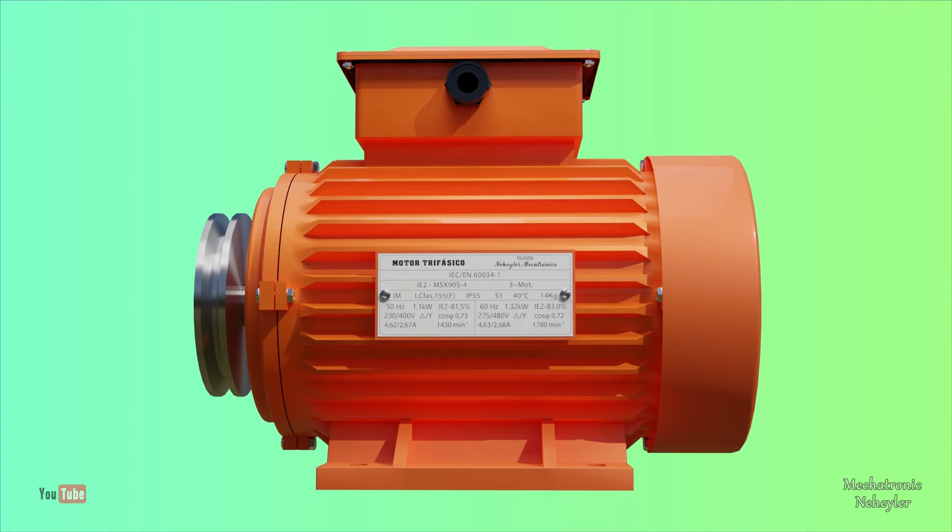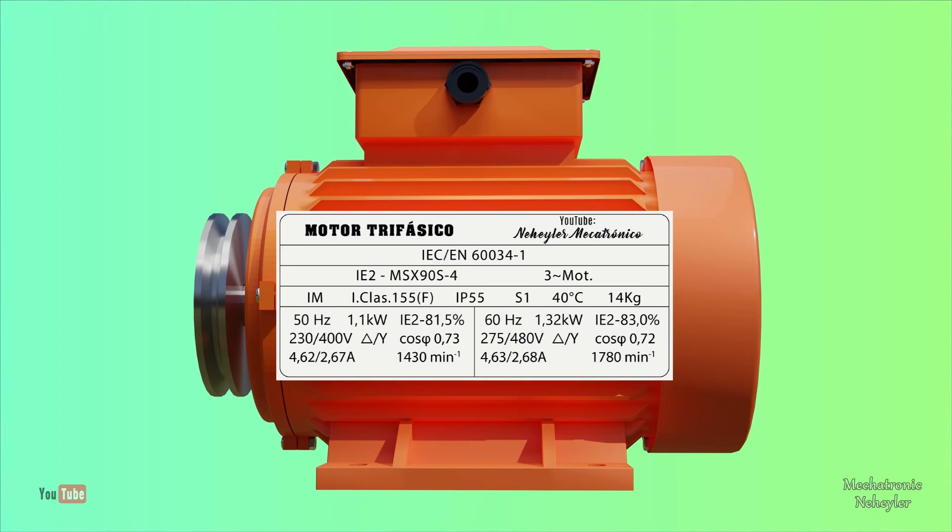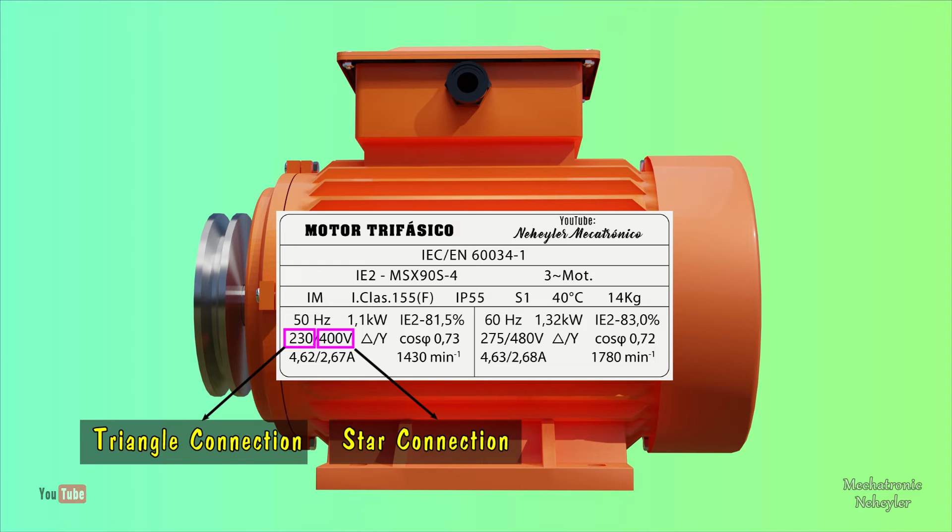On the data plate of the three-phase motor, two types of voltages are specified. Of which, a triangle connection must be made if you have the lowest voltage, in this case it indicates 230 volts. And a star connection must be made if there is a higher voltage, in this case it indicates that it is 400 volts.